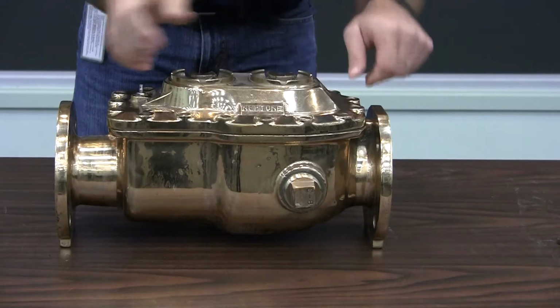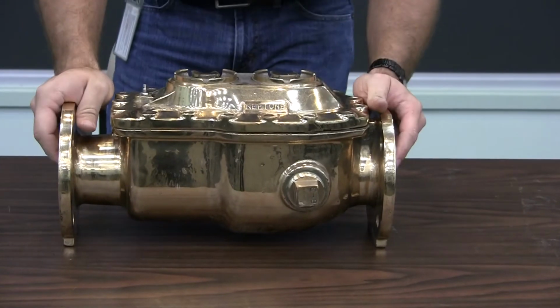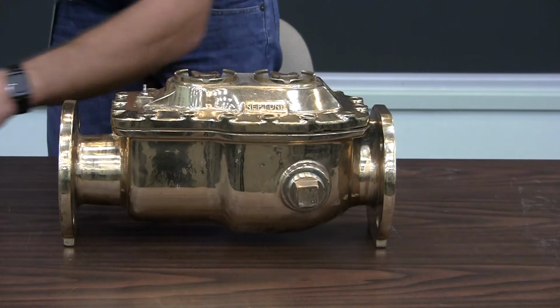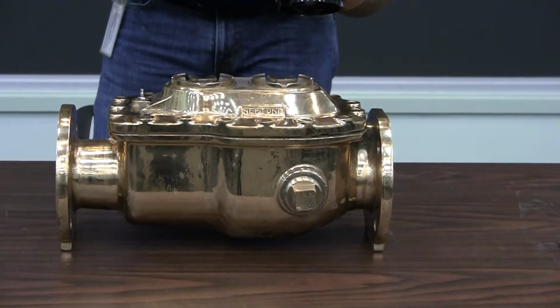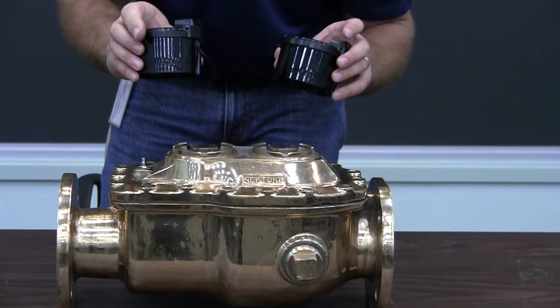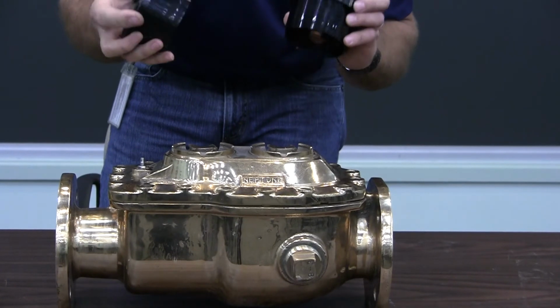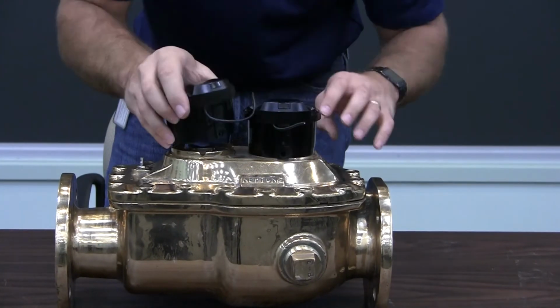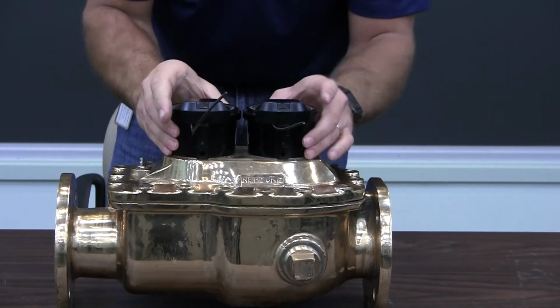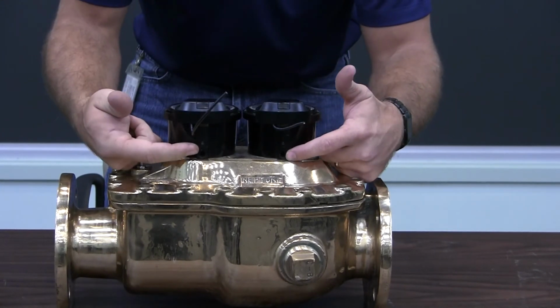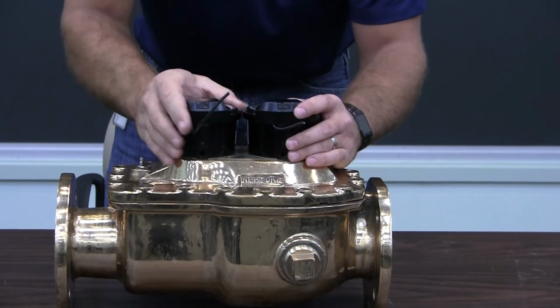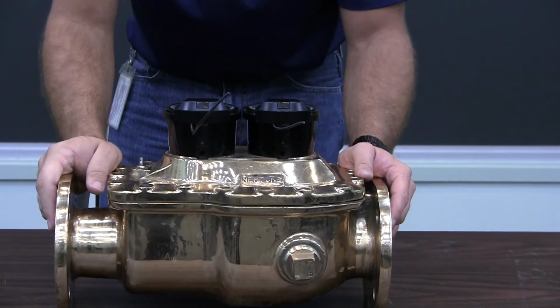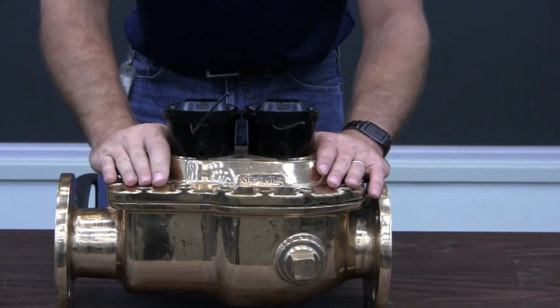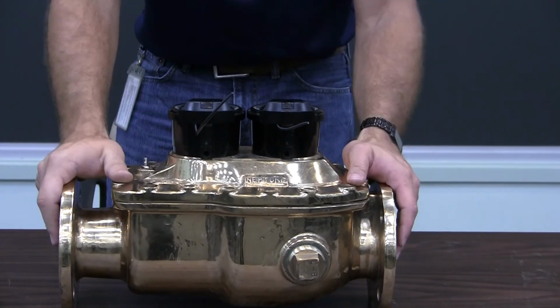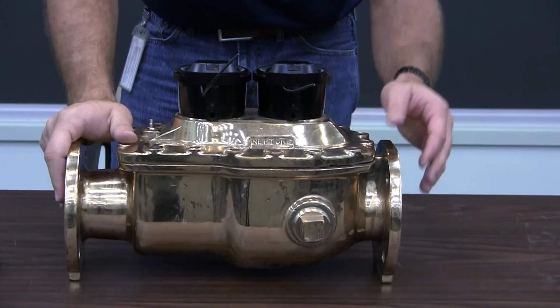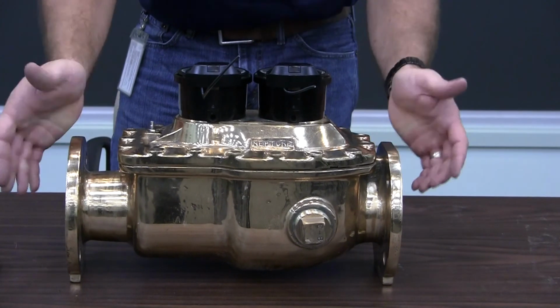to slide in. So now that we have our cover on our main case, we'll replace the registers, making sure that when you replace your registers that you put the turbine on the turbine side and the disc on the disc side, and to make sure the sizes match for the meter. Once you have these locked in, be sure to insert a seal pin to keep the register secure and to keep it from being tampered with on the meter. Now we have the main case and the cover all back together. We have a completed TRUFLO compound assembly. Only thing lacking is putting our bolts in, and that would complete the process.